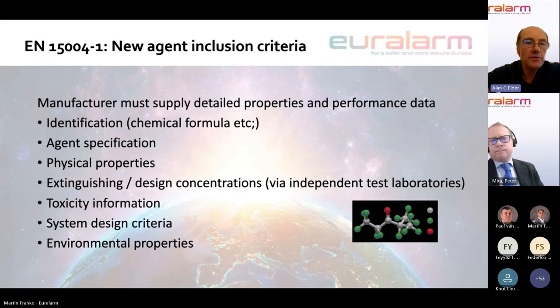And so in the revised version of the standard, there are some very important and critical data that must be provided by the manufacturer. And most of this must actually be independently assessed by test laboratories and third-party accredited. So the first thing is an identification of the material itself. What is the chemical formula? What is the specification for the agent? You know, what are the toxicity and the impurity profiles that are permitted for that agent to perform in the way it's designed to do?